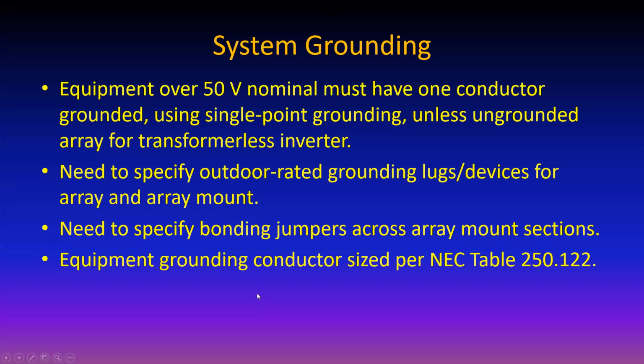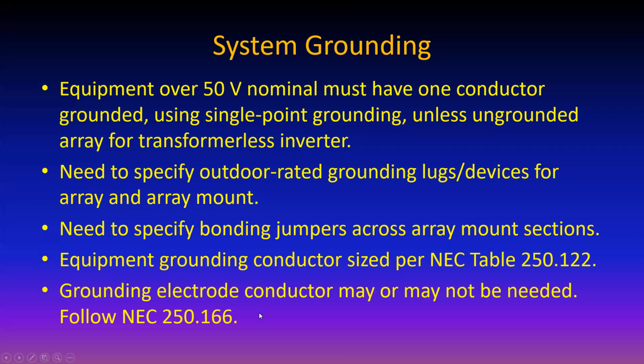Okay, so the grounding electrode conductor, you may or may not need it. You might be able to use a grounding electrode conductor that's already a part of the system, especially if you're backfeeding a breaker in the main panel. Or even if you're backfeeding a conductor in the main panel, you can generally just tie your ground wire to the ground in the main panel, and it'll be grounded by the existing grounding electrode conductor. Even if you're doing a line side or load side tap outside, a tap connection, typically there's going to be a ground wire in wherever you're tapping, and you can use the connection.